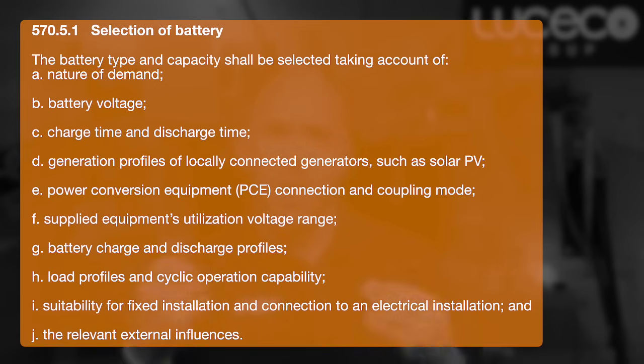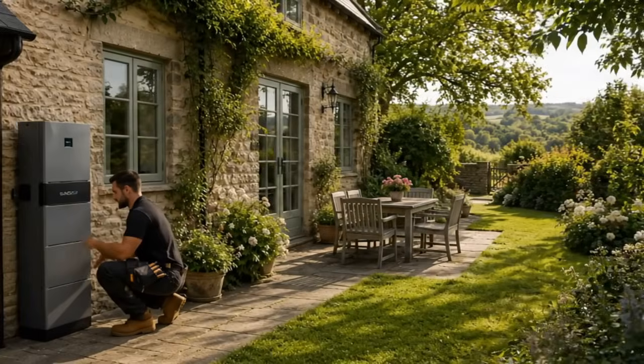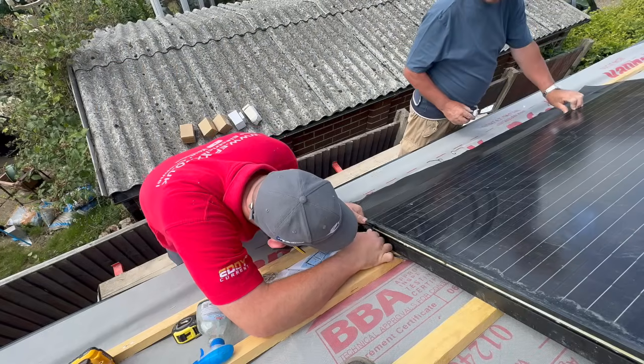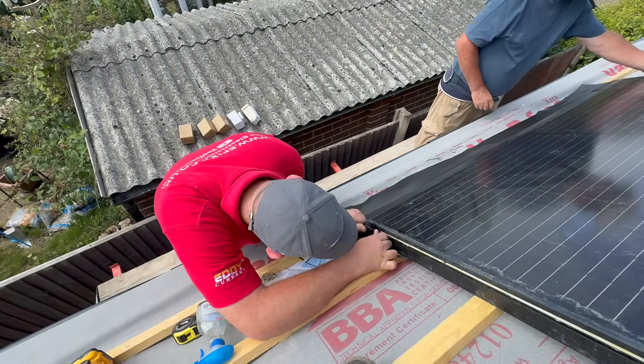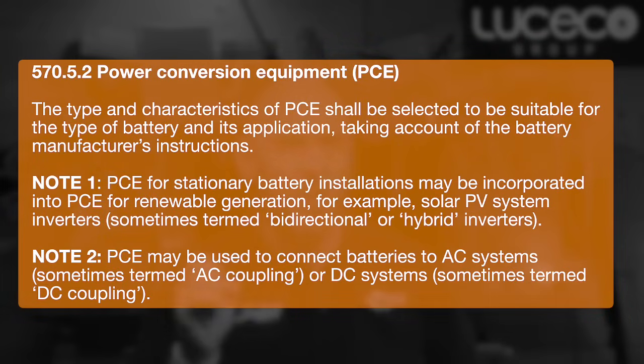That includes demand, load profiles, and any generation such as solar PV. So you are no longer just selecting a piece of equipment, you are deciding how that system is going to operate. The same applies to power conversion equipment, more commonly known as inverters. Regulation 570.5.2 requires it to be suitable for the battery and its application, taking account of the manufacturer's instructions.